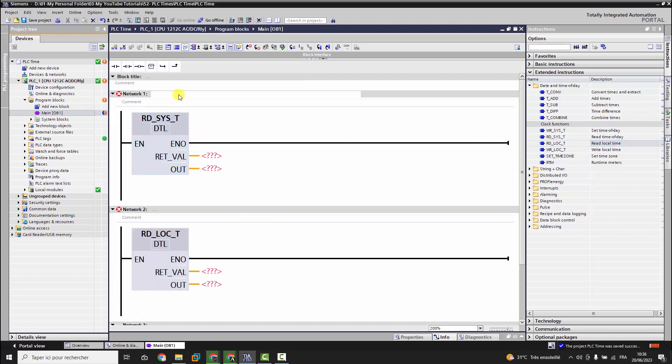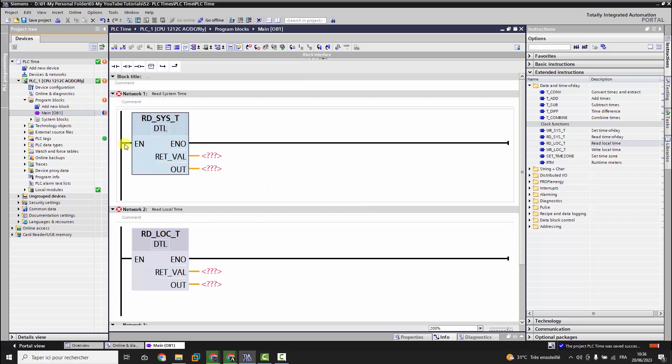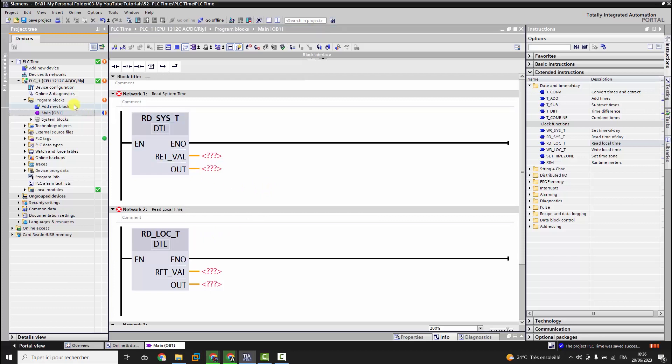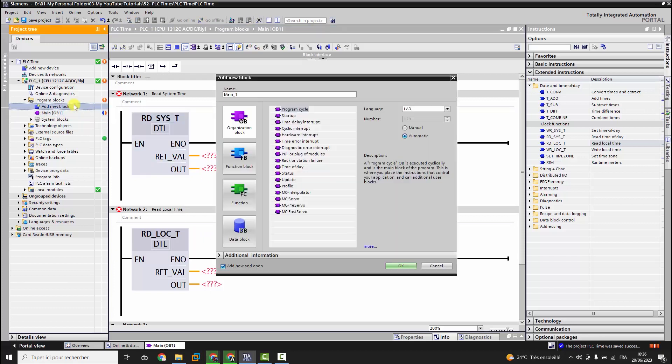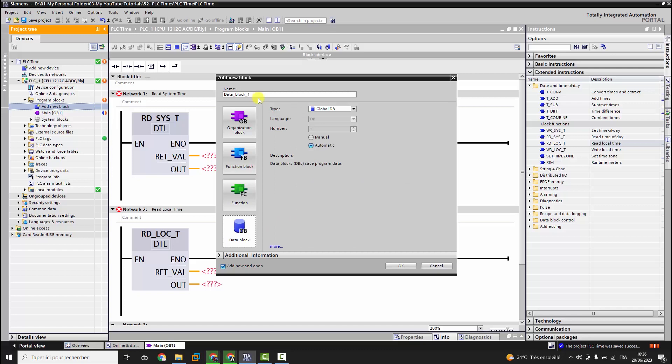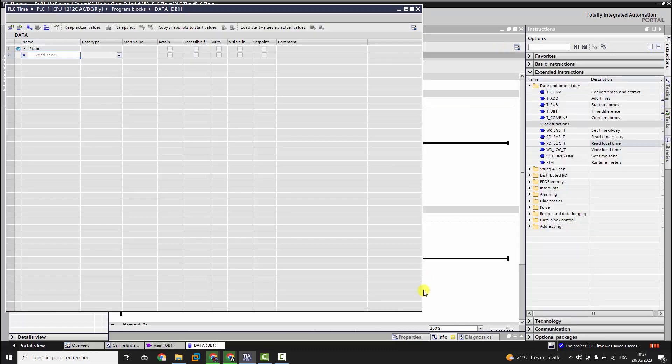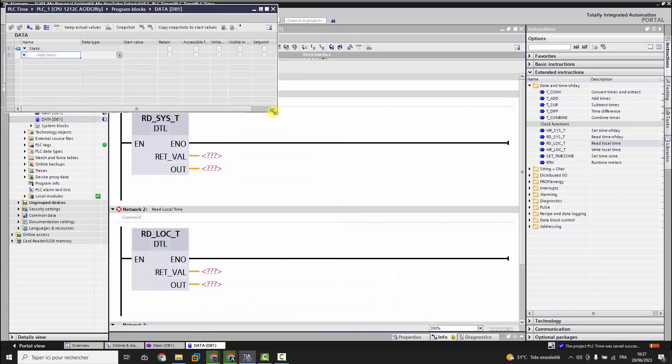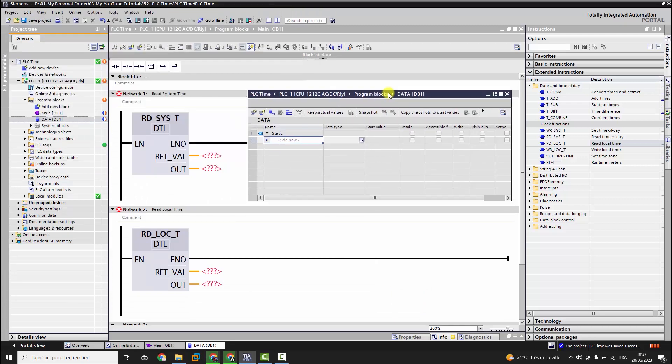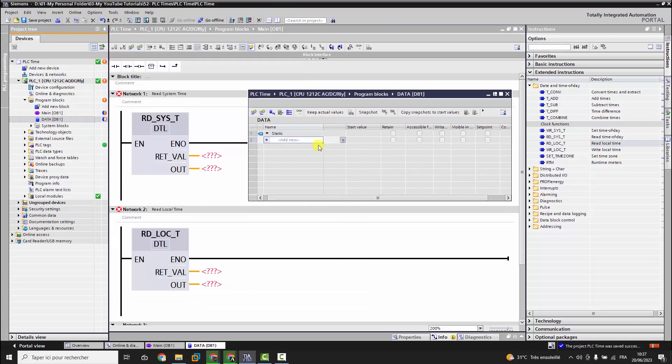The first block will read the system time. The second block will read the local time, and I will explain to you the difference between them. We will create a data block to define there all the tags needed for these two blocks. Every block demands two tags: one for the return value whereby we can read the error code of this block while it is executed by the PLC, the other tag will display the actual time.